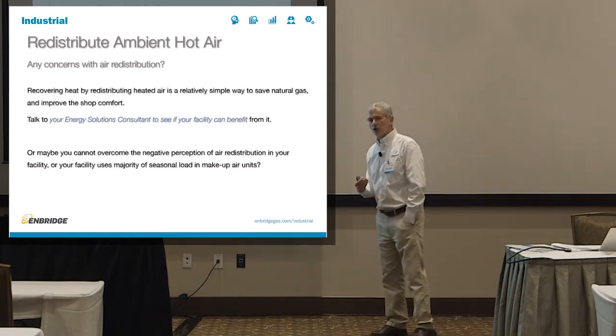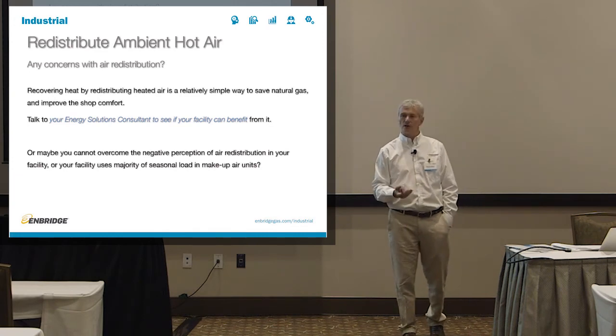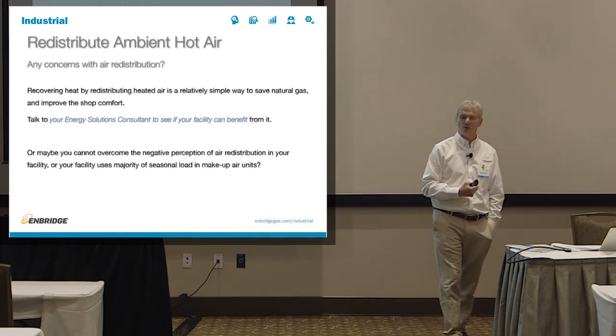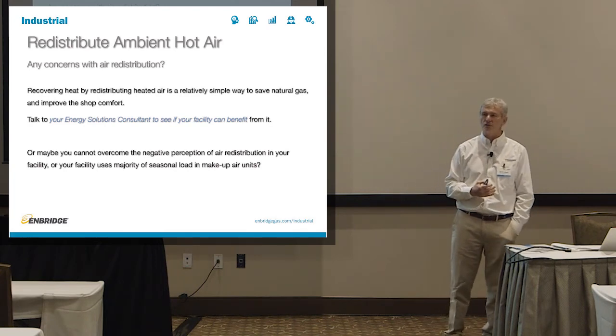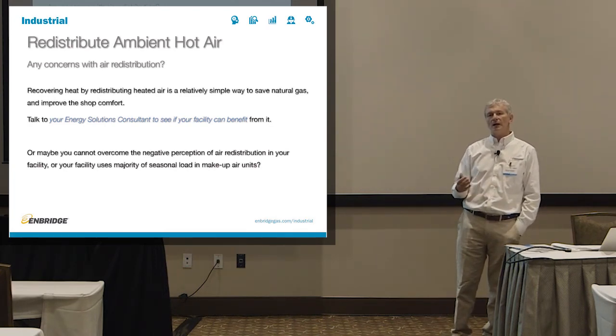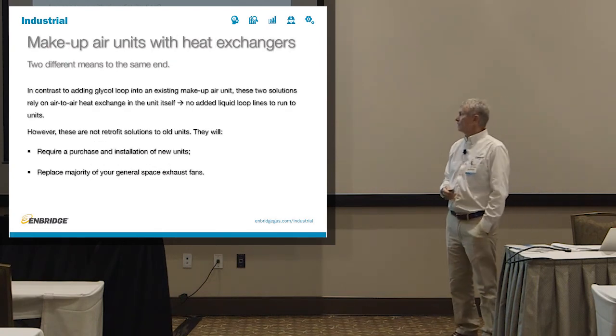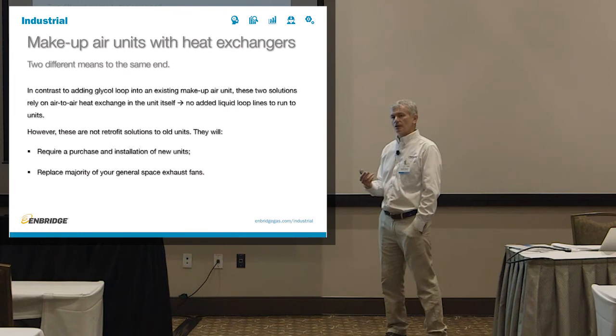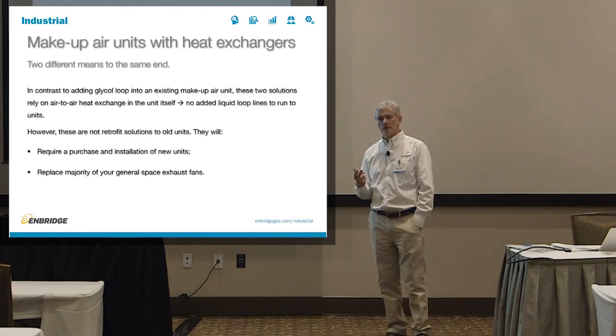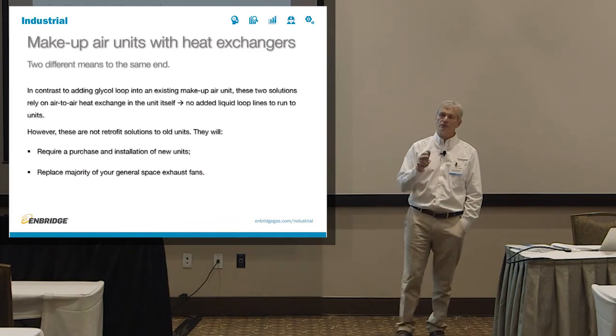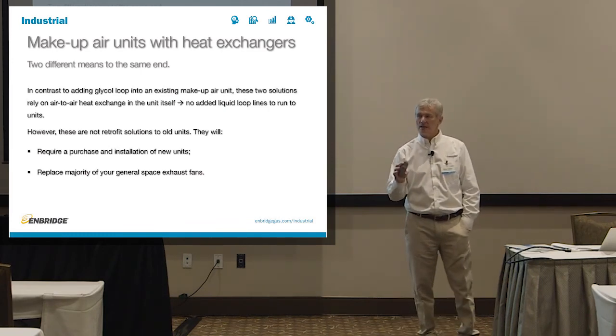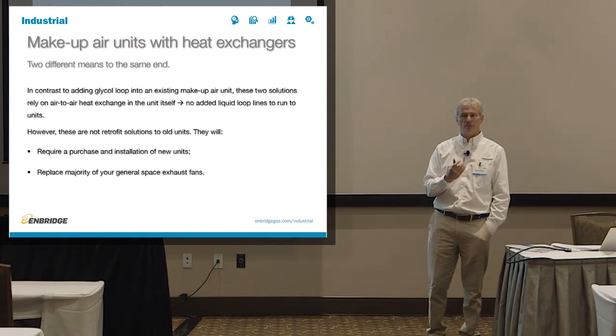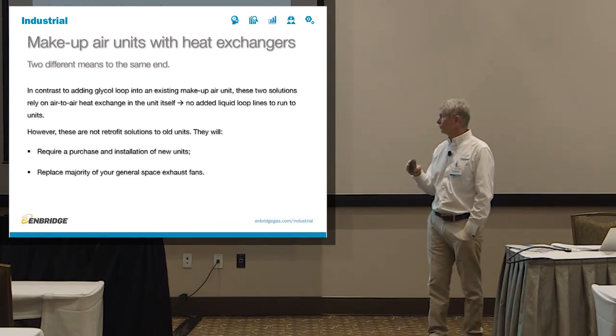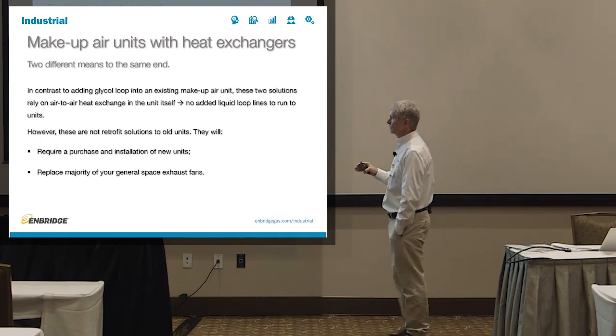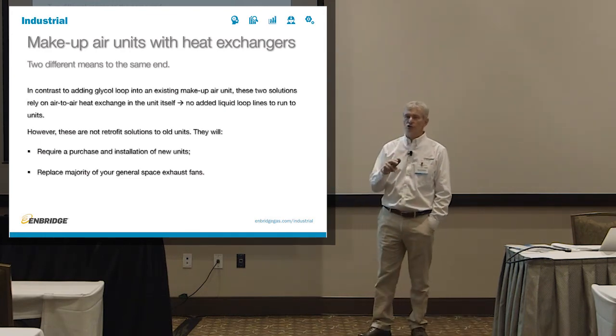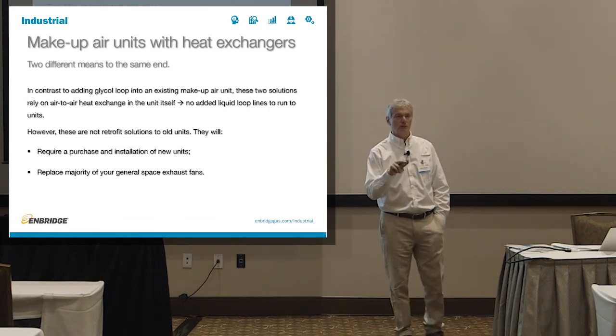What if you cannot do that? What if you cannot redistribute the air, either because the air quality is really bad or it's just not worth your while to fight the good fight of overcoming the perceptions? And your makeup air units are coming up to replacement time anyways. So there's a solution for that too. There are two different ways of recovering heat in your makeup air units if all you have is space heat that's escaping through the general exhaust. And we'll talk about both of them. Both of them require a purchase of new units, and both of them will replace the majority of your general exhaust fans. So both of those things need to be taken into account.